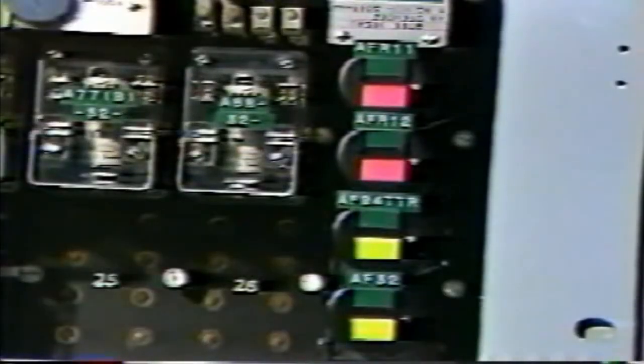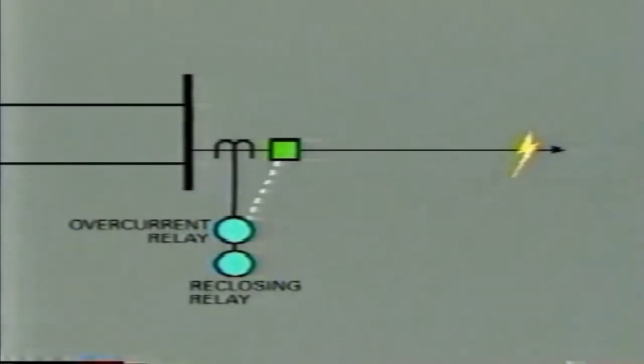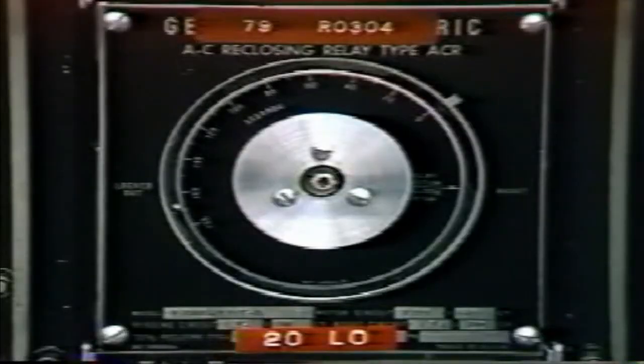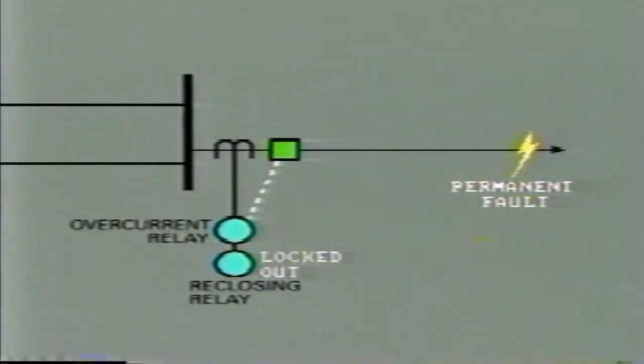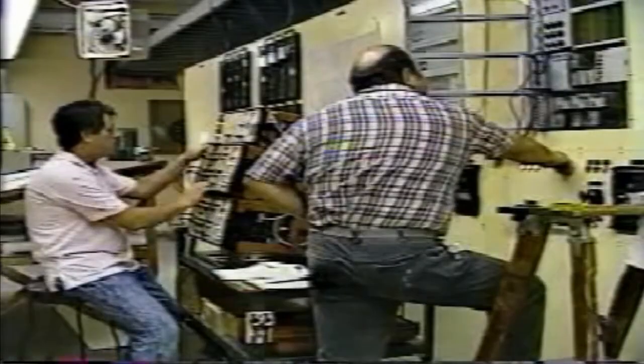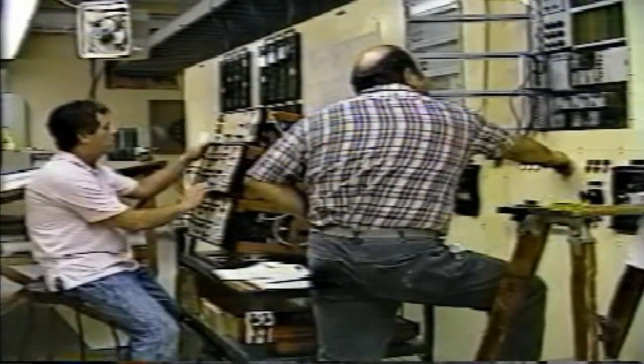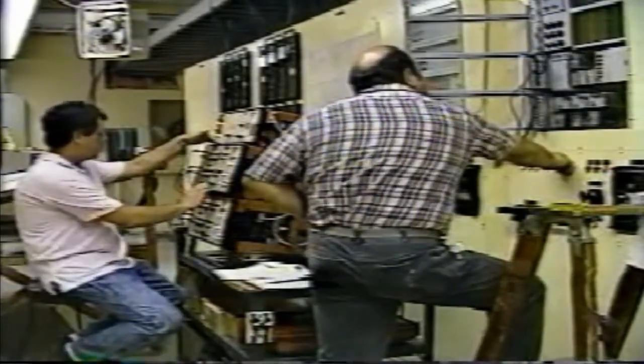If a line does trip out of service, the system operator will want to reclose that line as soon as possible. Of course, the reclosing relays will normally take care of this in the case of a temporary fault. You'll remember that we have discussed the role of reclosing relays in regard to system stability in an earlier tape in this series. However, if the reclosing relay locks out due to a permanent fault, cooperation will be needed with the relay department to decide the next move. Clearly, correct operation of protective schemes is a vital element in maintaining a stable power system.